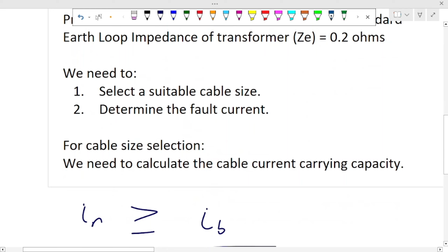So when we plug in the values, we'll get the cable current capacity. Then we'll go to the table for current capacity, the rated capacity for cable size, and check which cable size matches this value. That's the cable size we are going to select. So that's equation 1. For K1 and K2, you can also get those from the British standard table for the correction factor for ambient temperature and the correction factor for the British standard 3036 fuse.